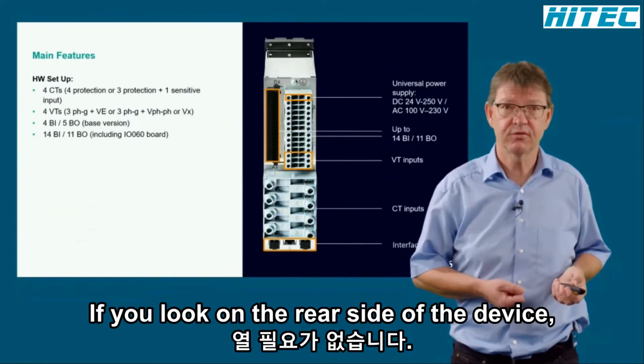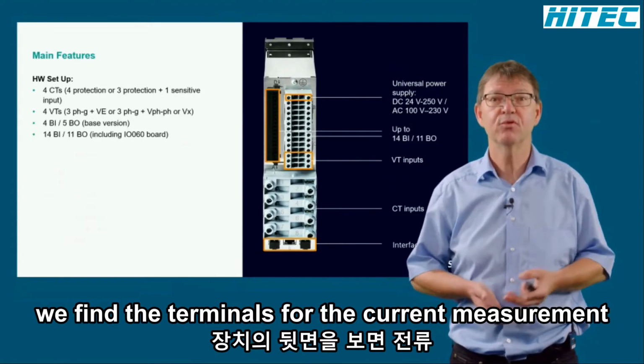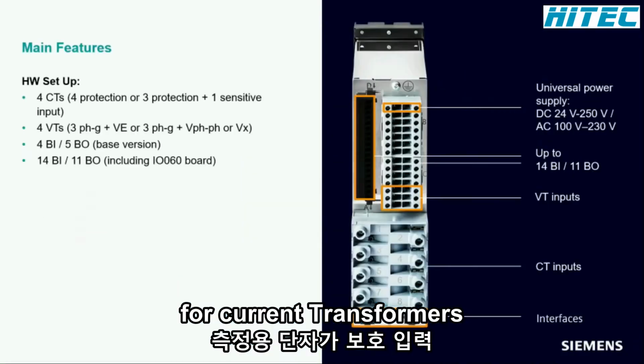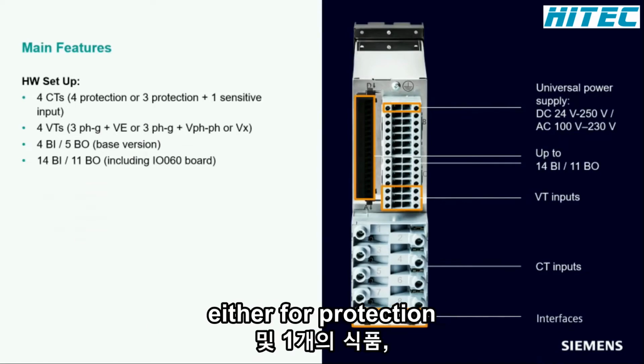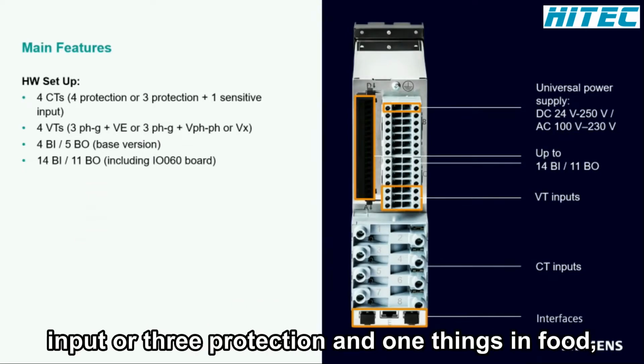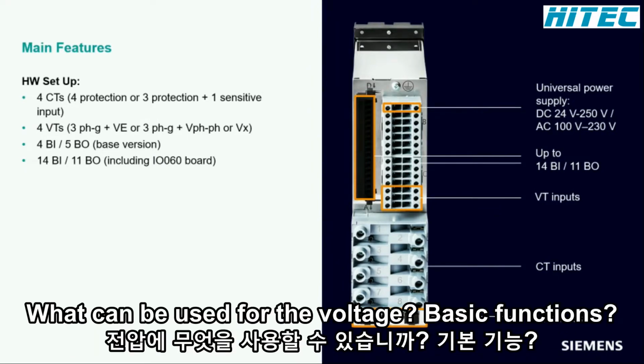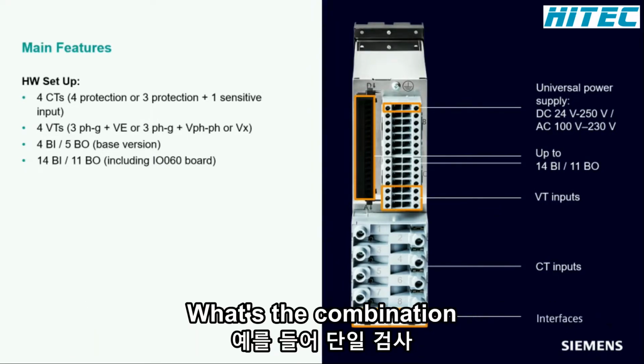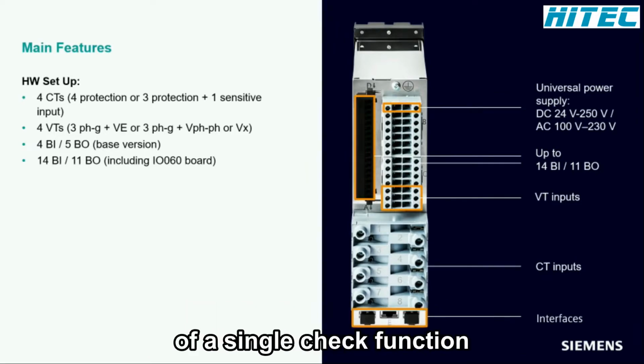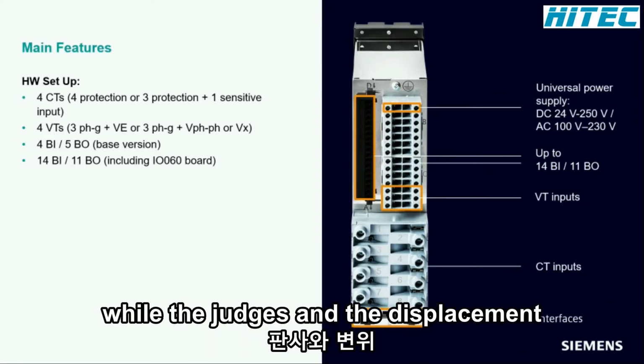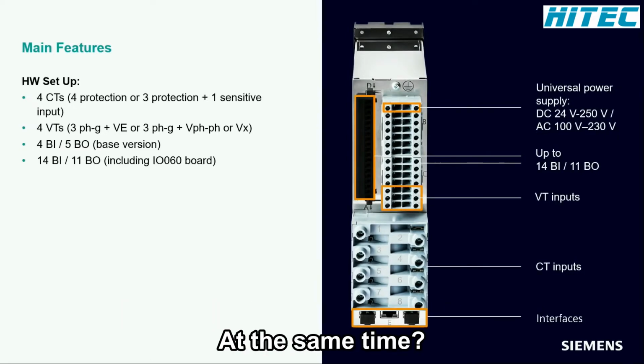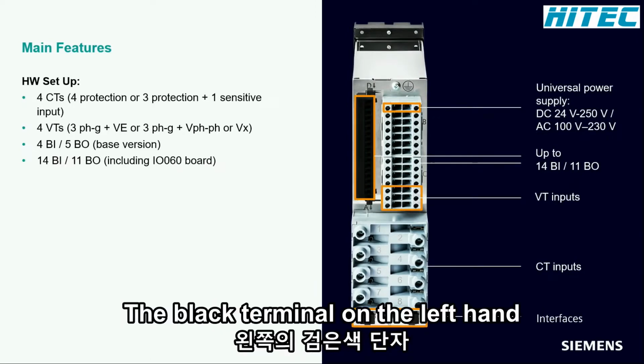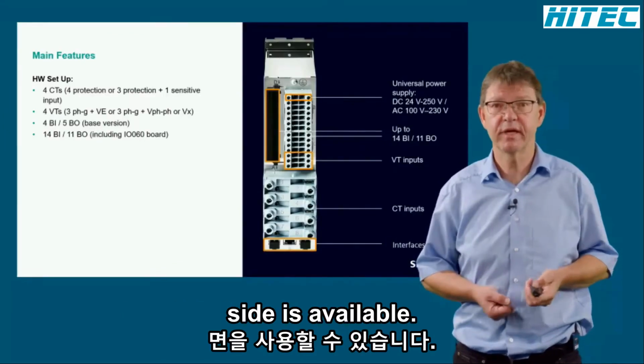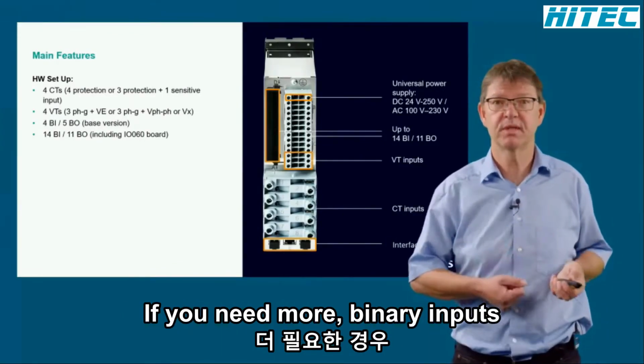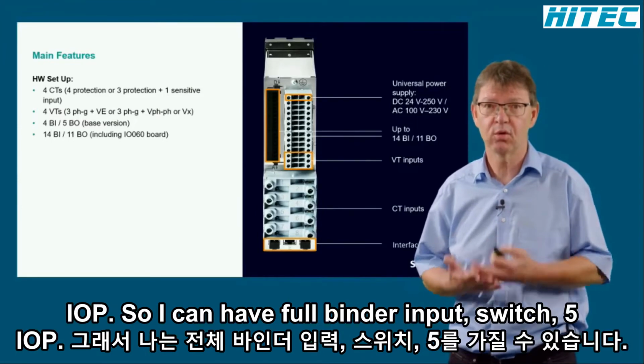If we look at the rear side of the device, we find the terminals. For the current measurement, 4 current transformers are available with 2 options, either 4 protection inputs or 3 protection and 1 sensitive input. The 4 voltage inputs can be used for the voltage-based functions, also for the combination, for example, of a synchro check function, the phase-to-ground voltages, and the displacement voltage protection at the same time. The black terminal on the left-hand side is available if you need more binary inputs and outputs via an additional built-in I/O board.